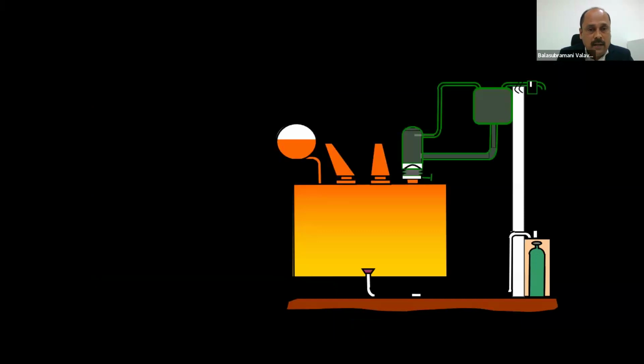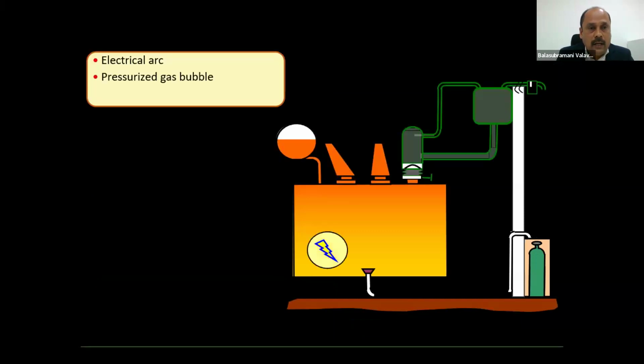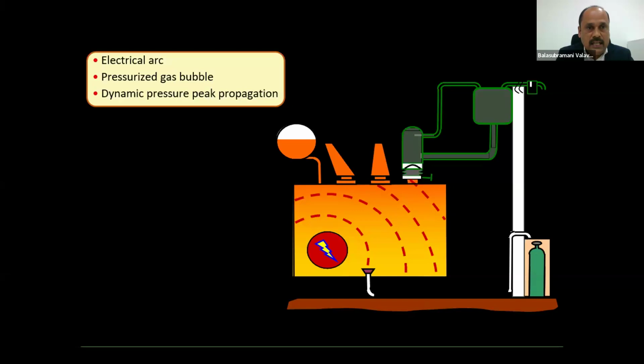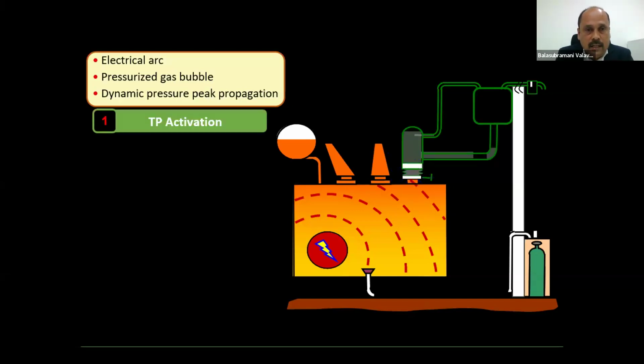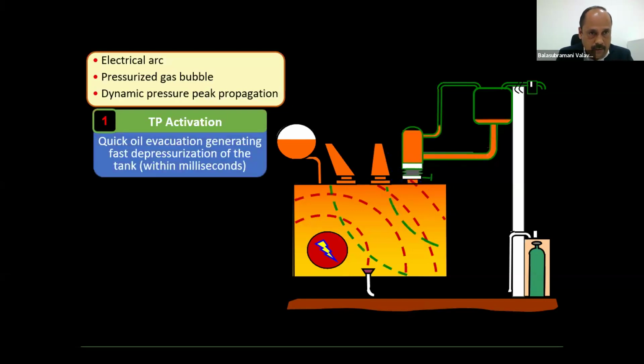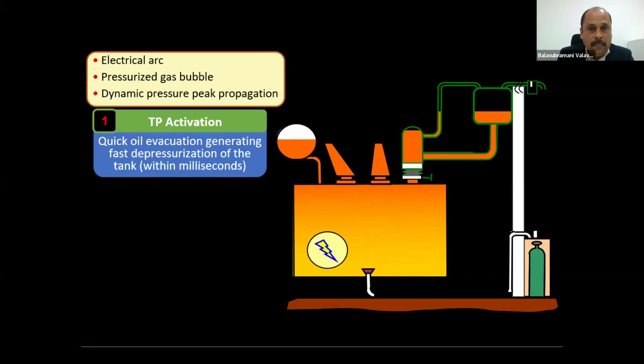Now here you can see how it works. Electrical arc, pressurized gas bubble, dynamic pressure is increasing, and here the TP is activated. Quick oil evacuation, the fast depressurization of the tank. So it goes and gets into the oil gas suppression tank. All the burnt gases will be taken outside.